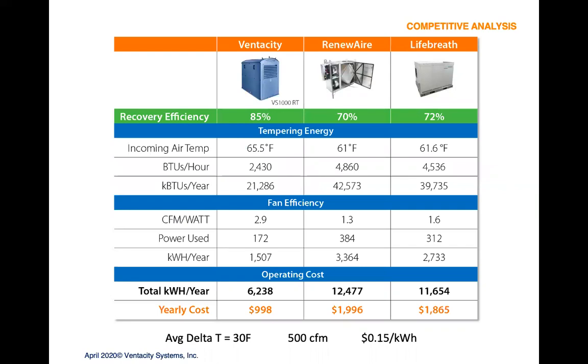If you take it one step further, this chart shows you, in the top section, 3 units comparing their efficiency, both for tempering or heat recovery efficiency and fan power efficiency. The first section is that tempering energy. I'm using a 30-degree delta T for a year round, just as an easy number, 500 CFM and 15 cents a kilowatt hour, just to give an example. Now you can change those numbers: the delta T temperature, the CFM, the cost, but the ratio is going to remain the same.